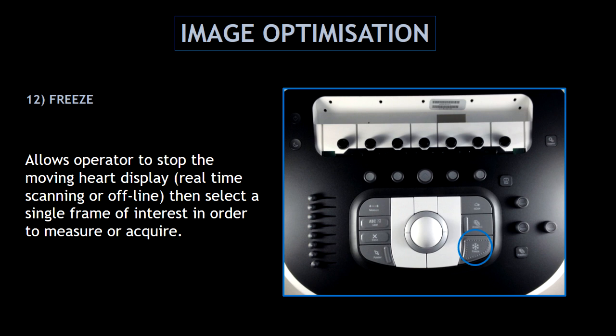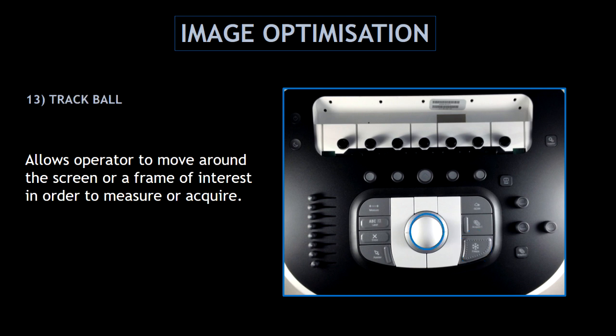Believe it or not, the freeze button is another image optimization feature, because this allows the operator to stop the moving image display and then select a single frame of interest in order to measure or acquire. Normally, we can find the freeze button next to the trackball. Our last feature and the most important one is the trackball, because this allows the operator to move around the screen and to select a frame of interest in order to measure or acquire.